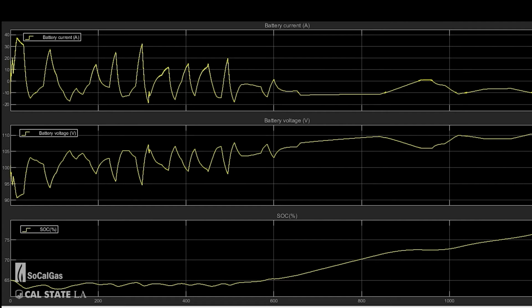The peak current is at 37 amps and the lowest voltage at 90 volts. We see at a moment where it discharges and charges quickly from 65% to 63% within 200 seconds. Like the standby charts, the fuel cell charges the battery here as well. The peak state of charge reaches up to 78.07% at the end of the 20-minute simulation. The voltage during charging stays above 107 and the current dips to negative 12 amps.